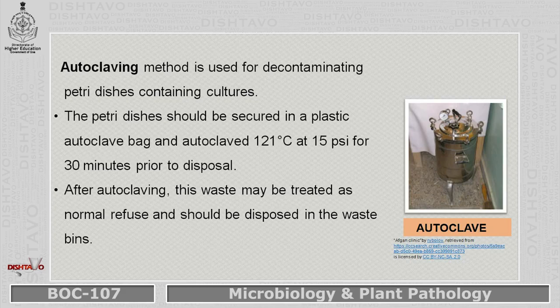The petri dishes should be secured in a plastic autoclave bag, and it should be autoclaved at 121 degrees Celsius, maintaining 15 psi pressure for 30 minutes prior to disposal. After autoclaving, this waste may be treated as normal refuse and should be disposed in the waste bins. This image shows the autoclave instrument.